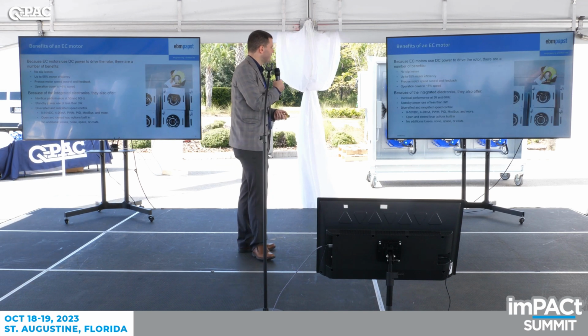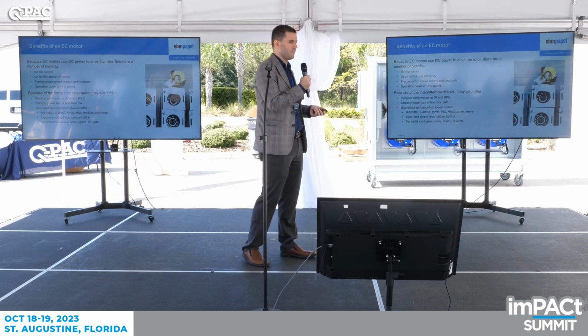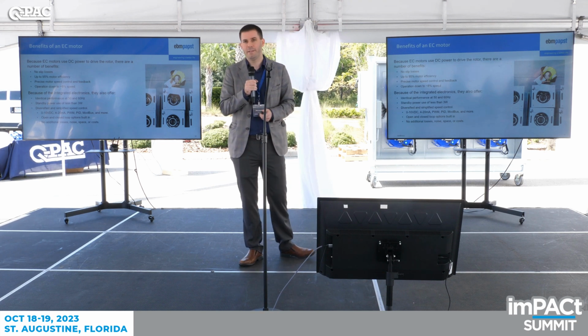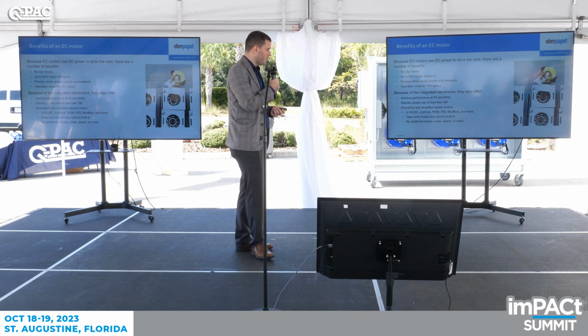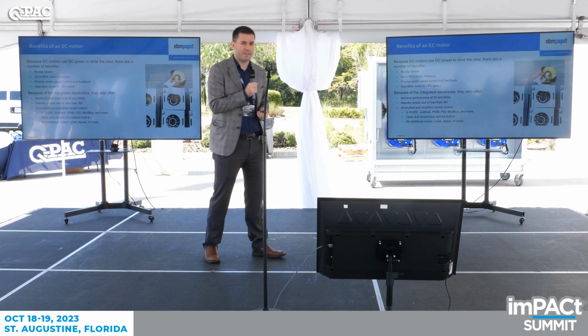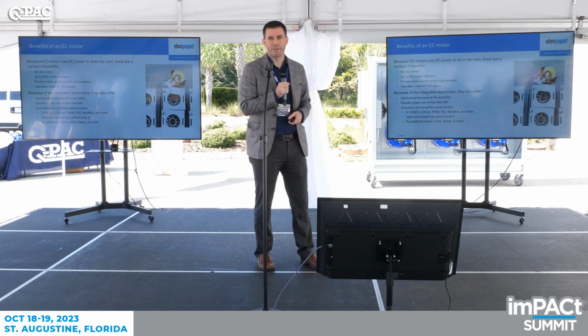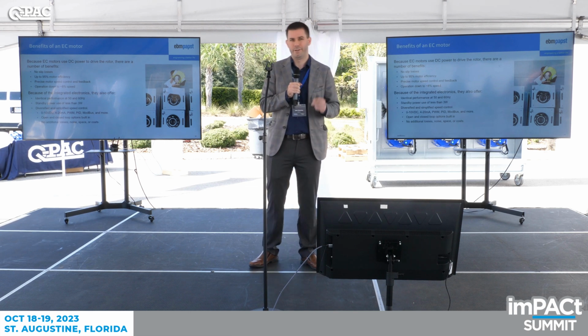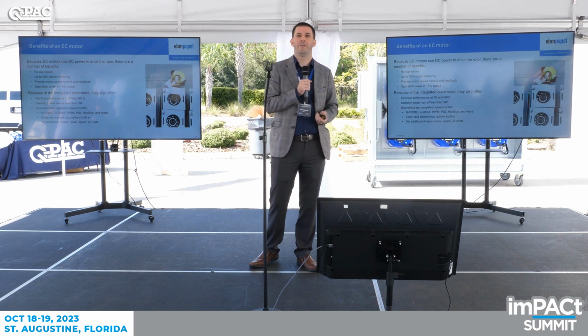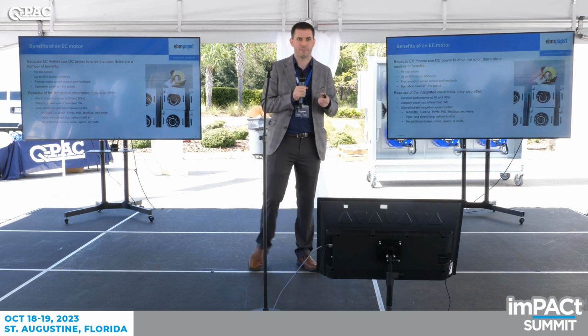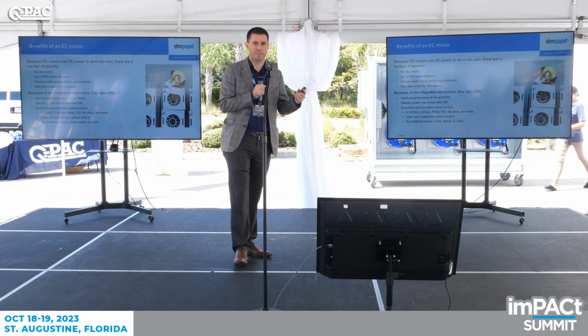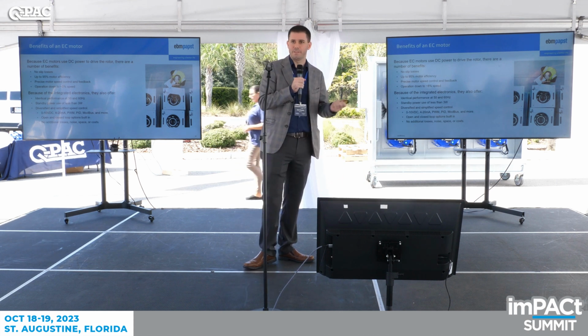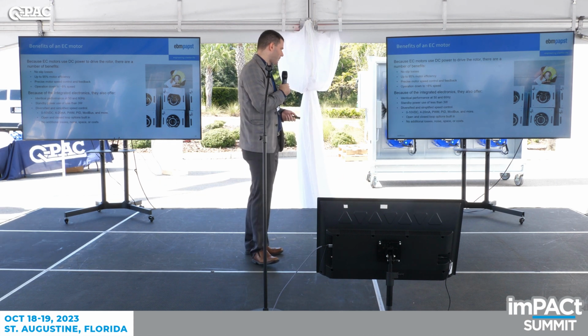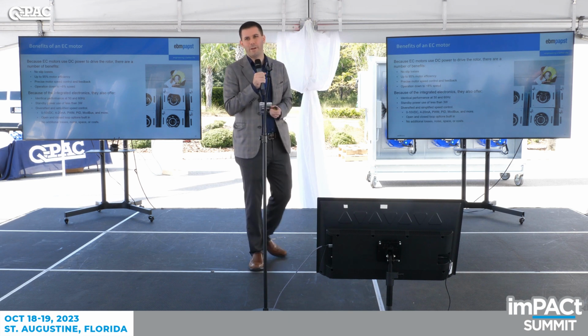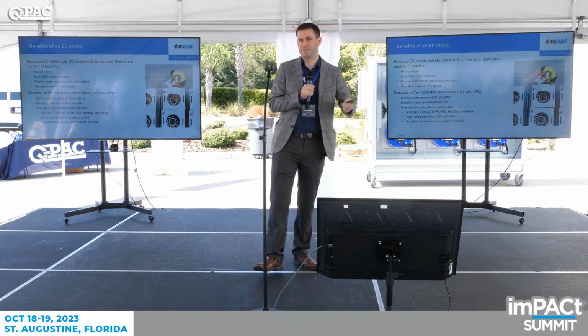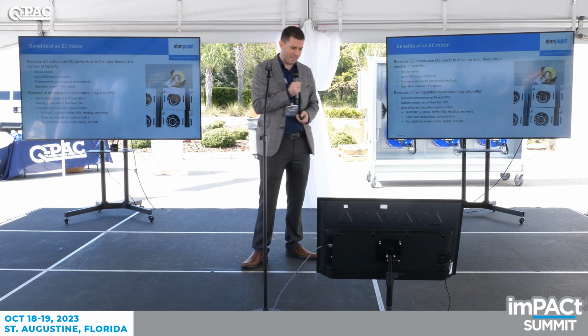Some other nice features: because it's a brushless DC motor, there are no slip losses. You don't have to worry about synchronous speeds or anything like that. Up to 95% motor efficiency. You get real precise motor control and feedback. You could actually put this in a closed loop speed control, and tell it, I want you to run at 1,495 RPM, and it'll run at that exact RPM, constantly monitoring itself, making sure that it's holding. Identical performance at 50 and 60 hertz. Standby power is less than 3 watts, and there are lots of different ways to control it. You could use 4 to 20 milliamps, 0 to 10, Modbus, BACnet, lots of options.